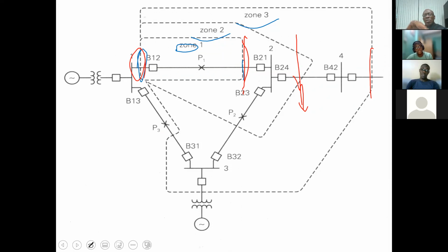And so like a good Jamaican, it will mind its own business, of course, depending on the parish you're living in. So it will mind its own business. However, as a good neighbor, if the fault continues, you're going to intervene. You call the police and say, boy, something going on. So them quarreling next door, in terms of a fault, you ignore it. But if it continues, you trip. So you give them 15 minutes to quarrel. But if the quarrel continues for 20, you intervene.